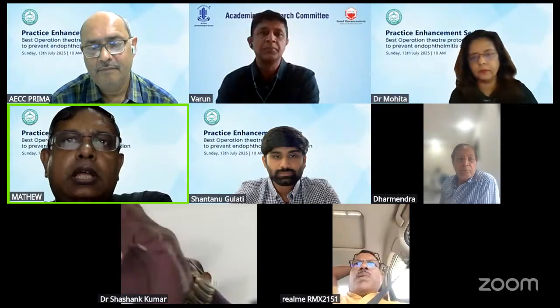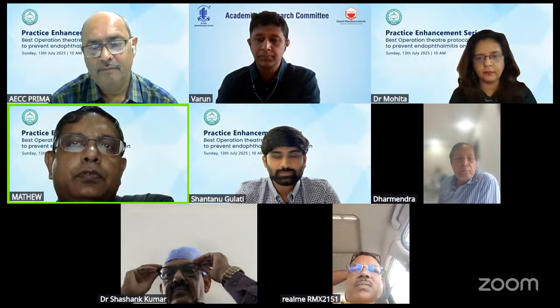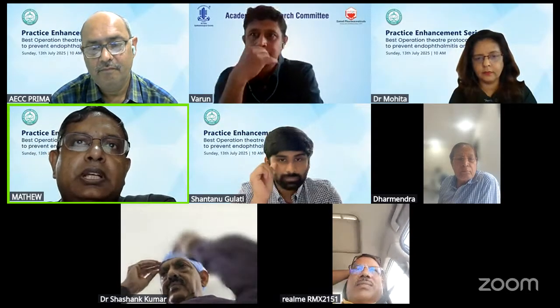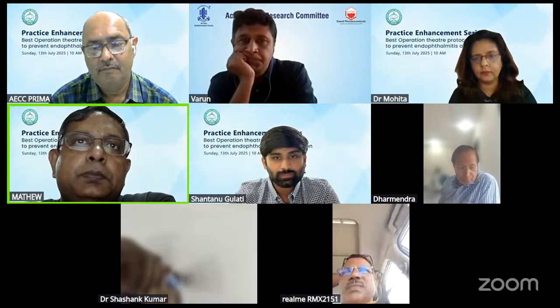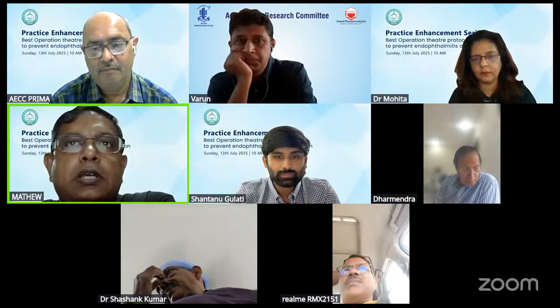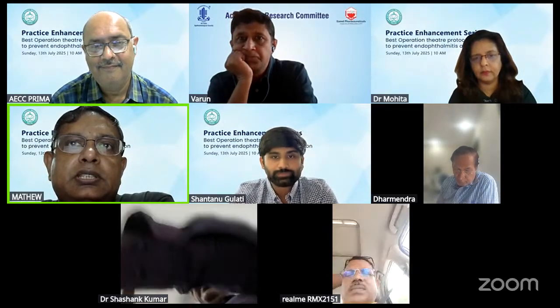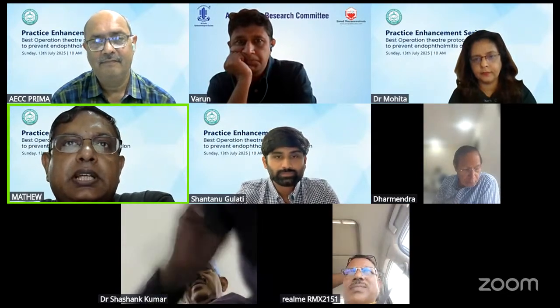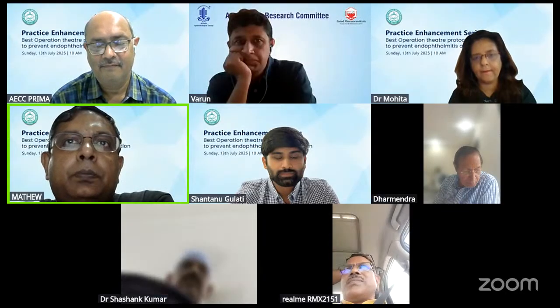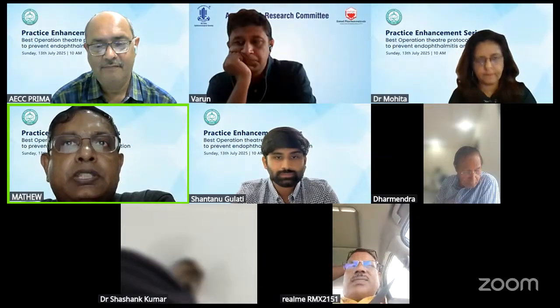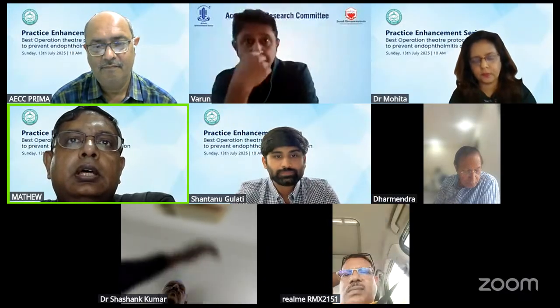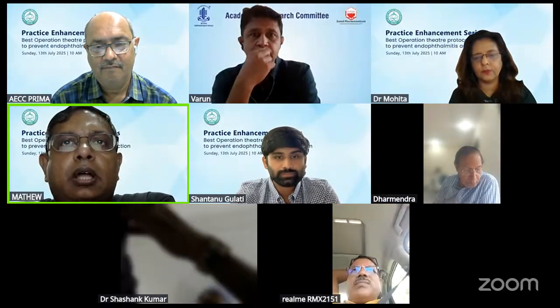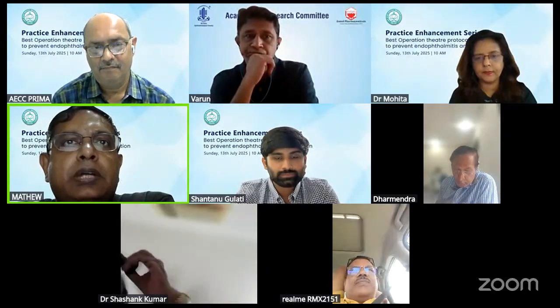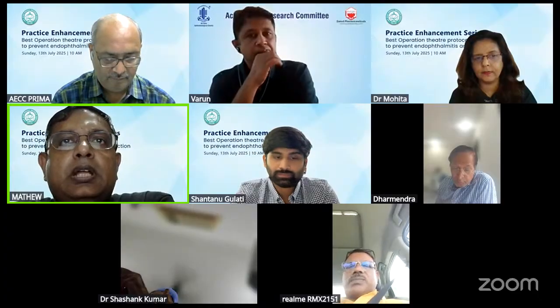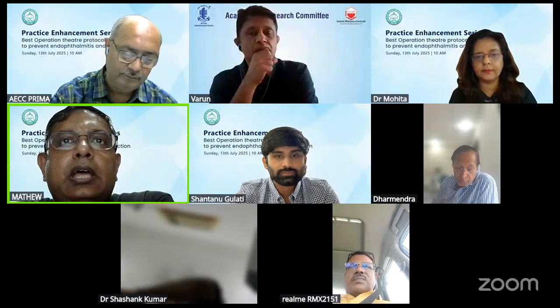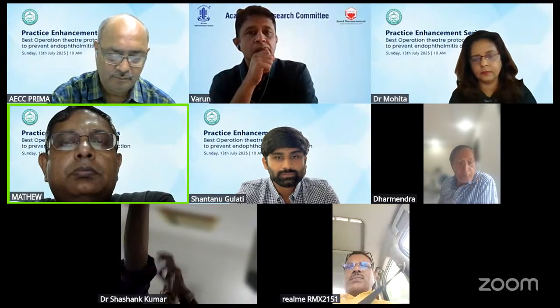Yes. NABH's requirement, from the point of view of documenting that your AHU is working properly or your air quality is acceptable, is that there should be a daily log of temperature, relative humidity, and pressure. Positive pressure is required. The temperature should be between 21 to 24 degrees centigrade, and the relative humidity should be maintained during operational hours at least between 45 and 55% RH. We should have the daily log. The validation, typically by an external agency, should document that we have at least more than 20 air changes per hour, and that is actually a calculation. And the recirculation of air should be not more than 80%.